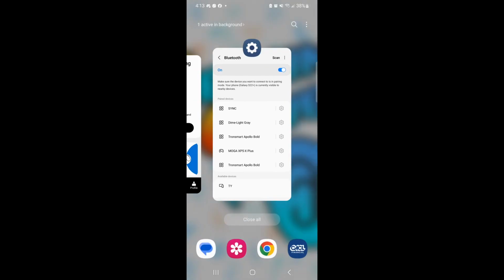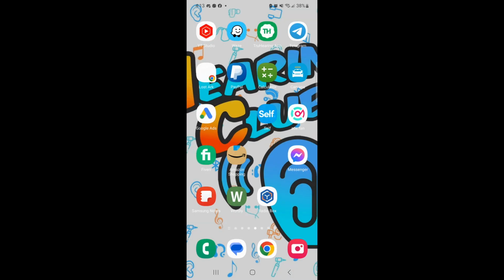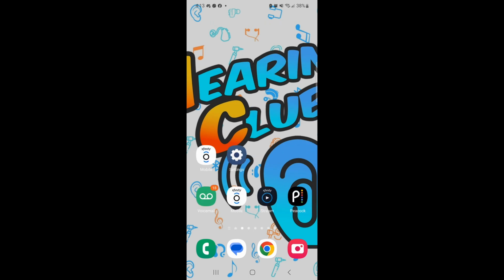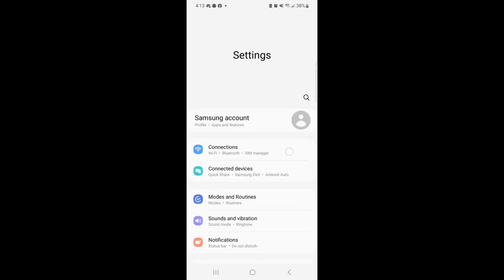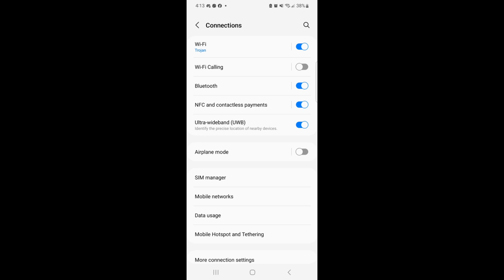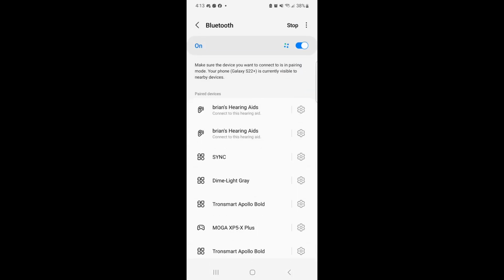And now we're going to go back into the settings and go to the Bluetooth menu, and we're going to also unpair them from the Bluetooth menu. And there you can see the hearing aids. They're still paired. Now, you have a couple options here. You could either connect or disconnect the hearing aids, but that's just going to disconnect them temporarily. We want to completely remove them from the phone. So we're going to hit the gear icon on the side. This is very important. And we're going to hit unpair.